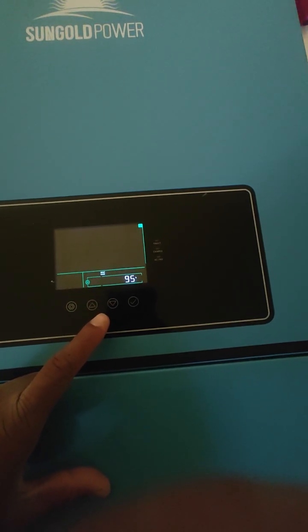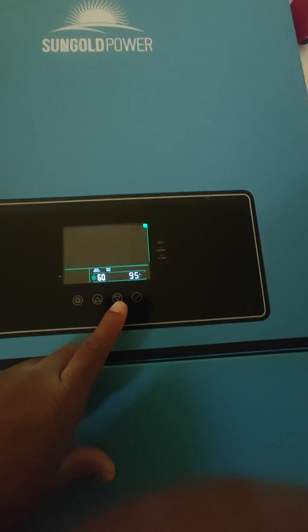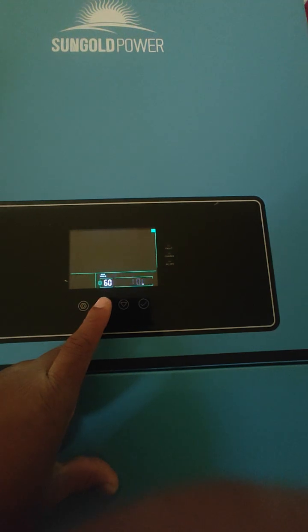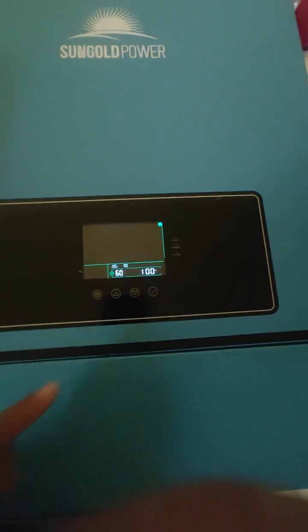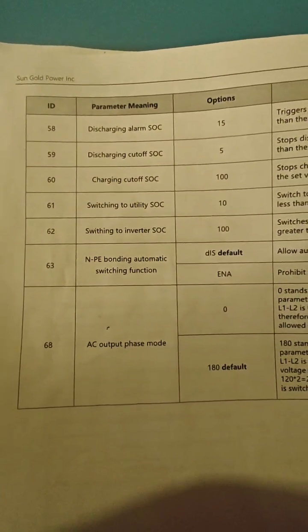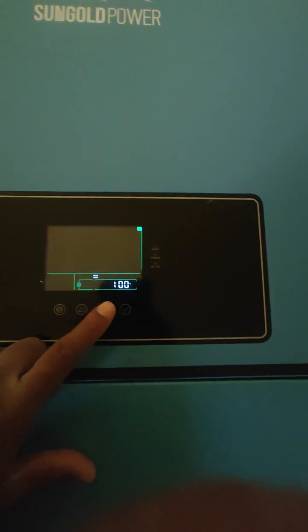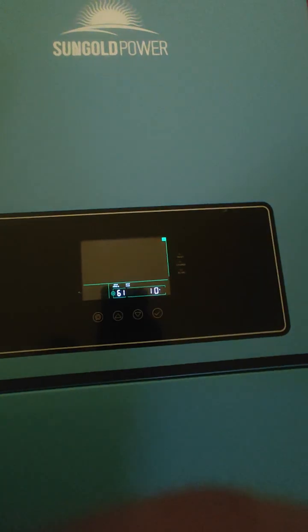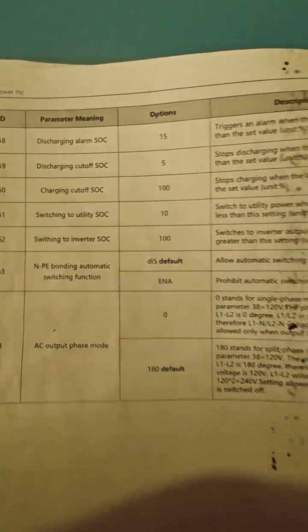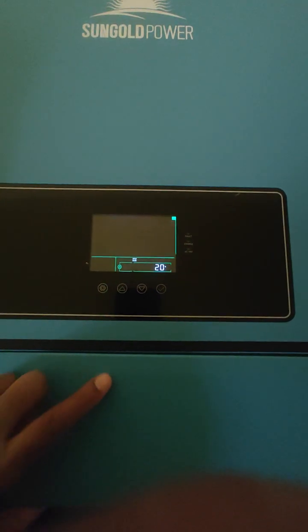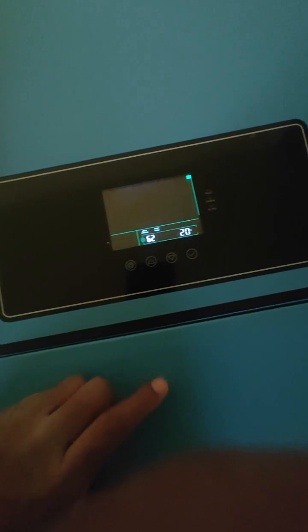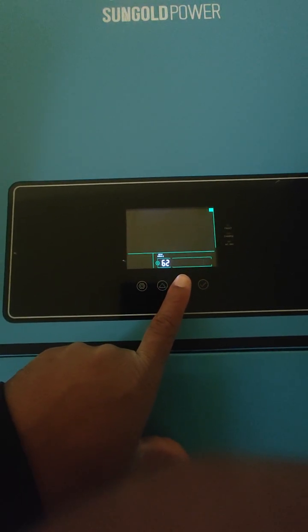Charging cutoff SOC state of charge. So stops charging at, I don't know why that's 95%, but we stopped charging at 100%. 61, switching to utility state of charge. It's 10%, which is fine. Switching to inverter state of charge. Let's see. Should be 100 as the default. So let's go down there.